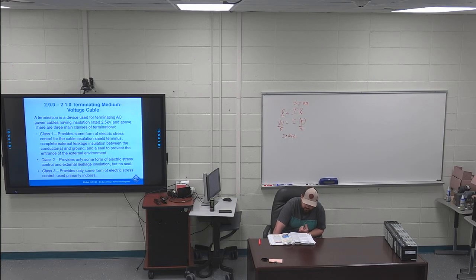You have to have a seal to prevent the entrance of external environment into the cable and to maintain the pressure, if any, within the cable system. That class 1 termination is the only one that's going to be able to seal against external environment stuff. On the right hand side of page 24, I've got the first sentence of the class 3, or the 2nd bullet point on the right hand side of 24 highlighted. First sentence: a class 3 termination is the one that provides only some form of electric stress control for the cable insulation shield terminus.